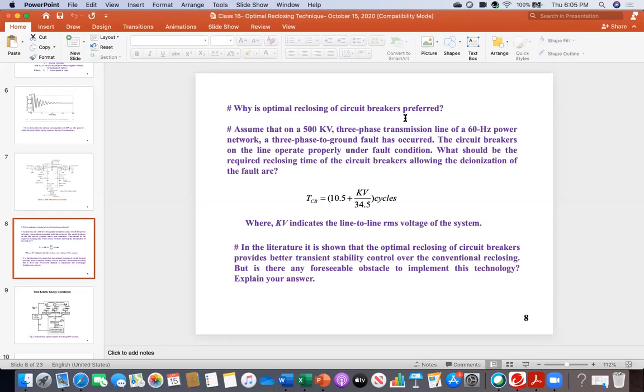So then what is the conventional method? The conventional method is based on fixed timing. Conventional reclosing also looks at arc extinguish time, but it is fixed, saying let's reclose after 50 cycles or 30 cycles. Depending on the network and country, there are various rules, every country allows that waiting time until arc extinguishing. But after that, it is kind of fixed and conservative. This means if it were reclosed much earlier, as I've noticed through simulation...